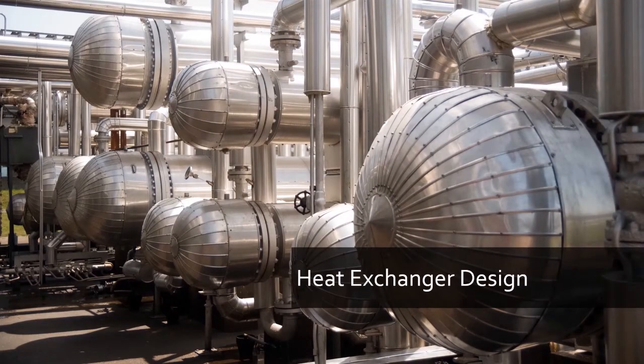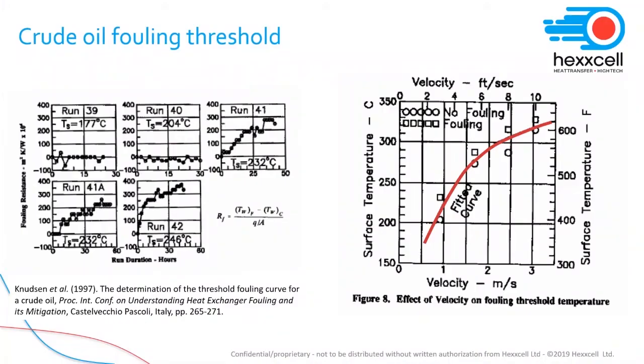So let's see what can be done by using data to better design heat exchangers. We have seen the limitation of the use of fixed fouling factors at the design stage, and we said that artificial intelligence plug-and-play does not work. So if we want to go beyond this, what do we use? There is experimental evidence that there are certain conditions of temperature and velocities at which fouling does not occur. What I'm showing here is an example for crude oil fouling from Knudsen and others, where they ran an experimental facility and determined the conditions at which certain crudes were fouling and those at which they were not. The threshold is shown in red on the right-hand side and can be represented with an equation that will therefore provide values of fouling as a function of process conditions and time, instead of using a single fixed number that lumps together several assumptions.